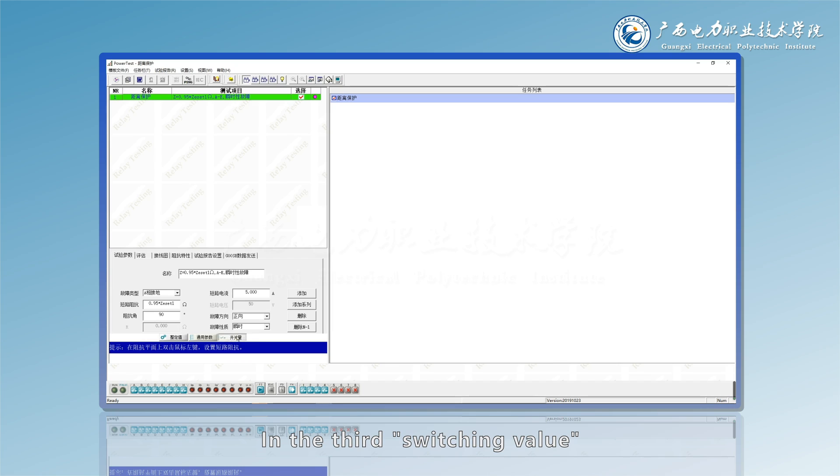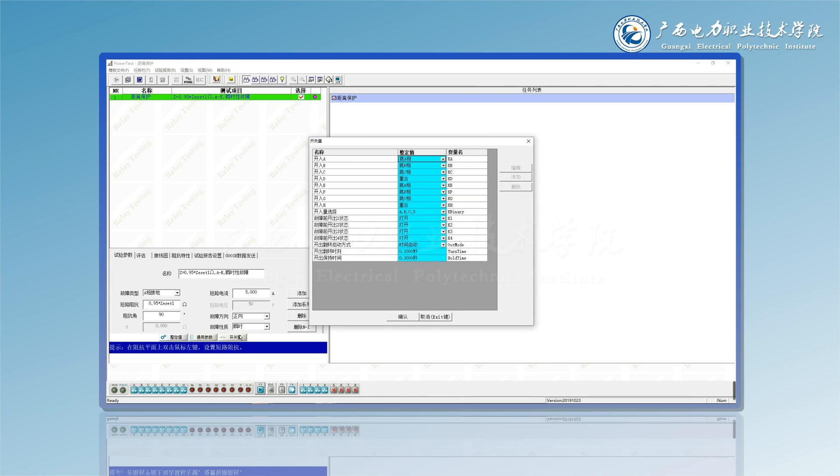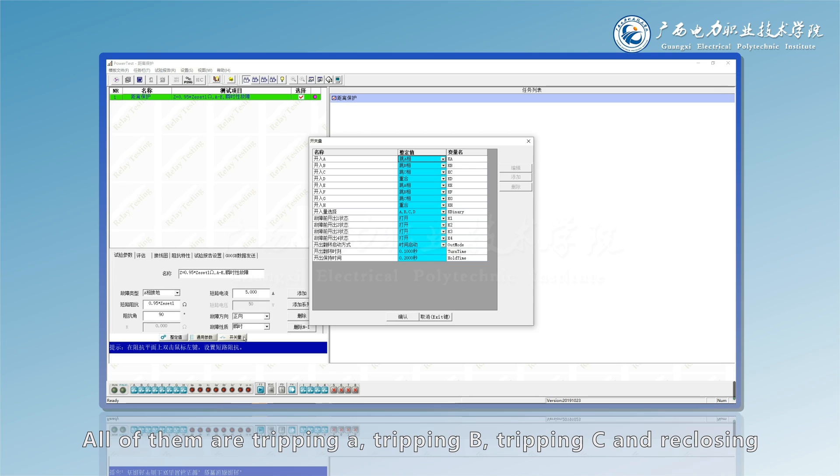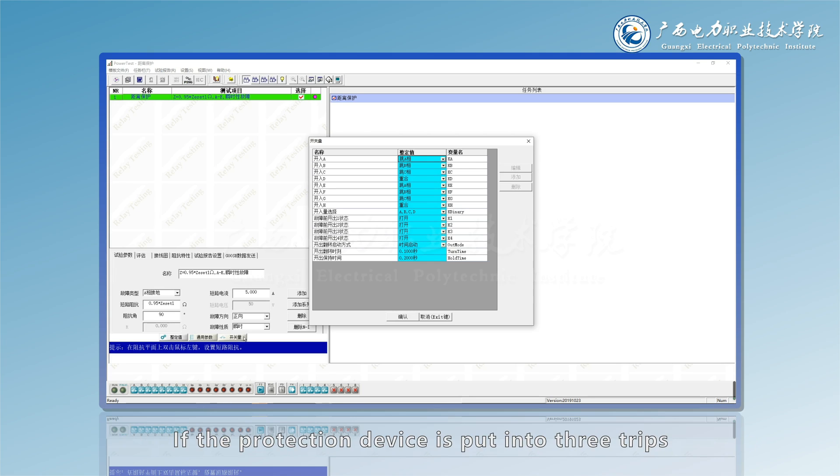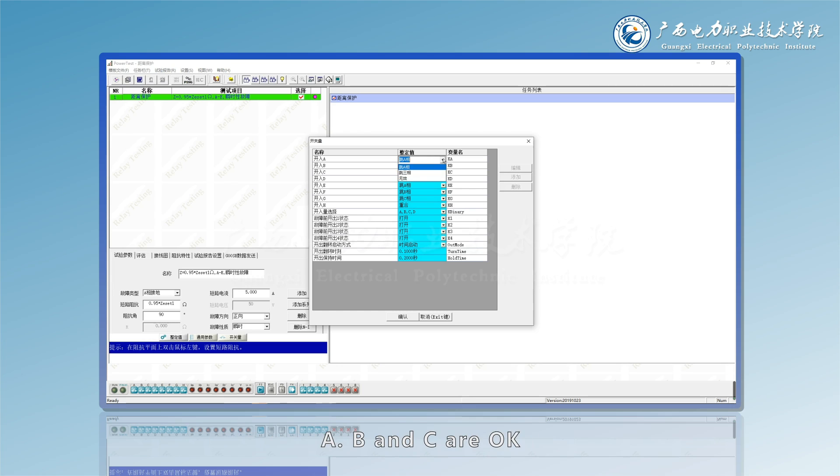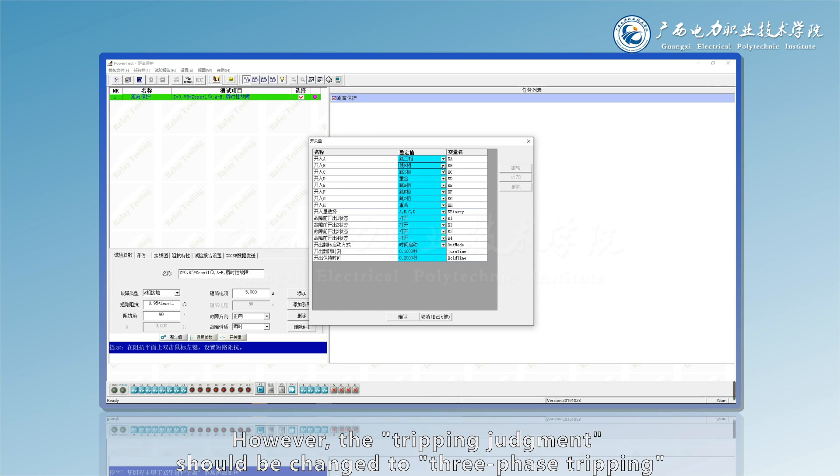In the third switching value, the tester has eight pairs of switching value contacts. In line protection, it is defined as two groups of tripping contacts. By default, all of them are tripping A, tripping B, tripping C, and reclosing. If the protection device is put into three trips, then only one trip contact is required. A, B, and C are okay. However, the tripping judgment should be changed to three phase tripping.